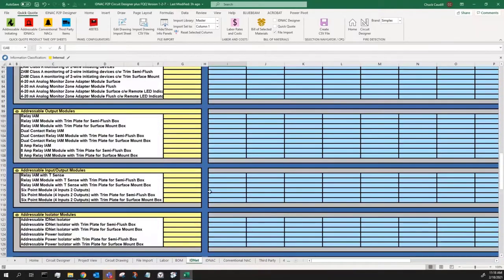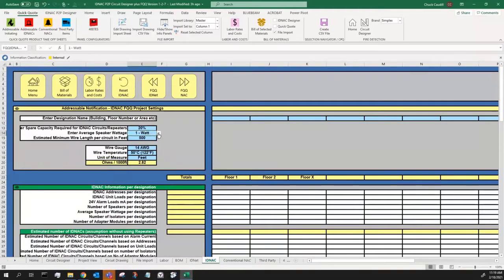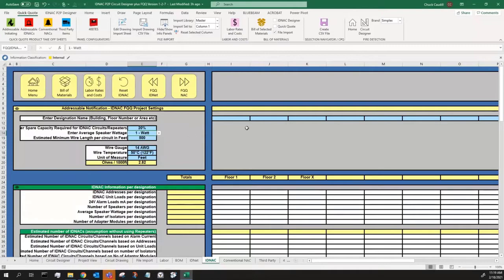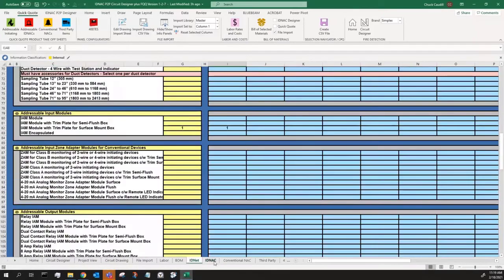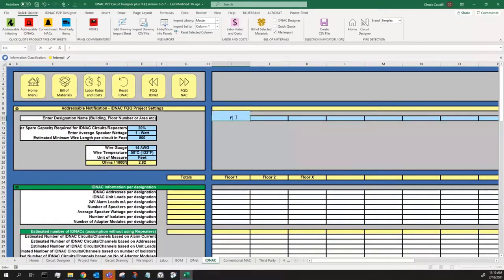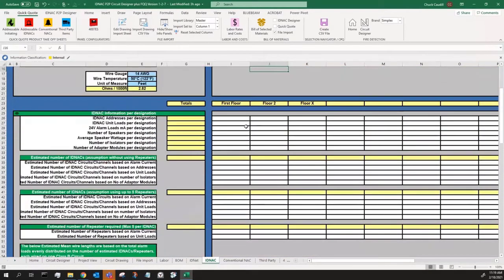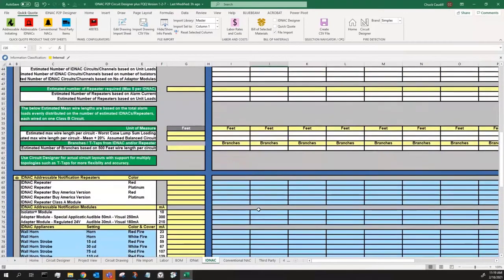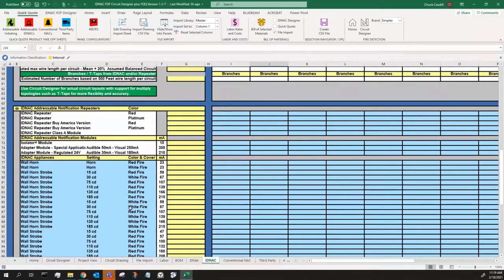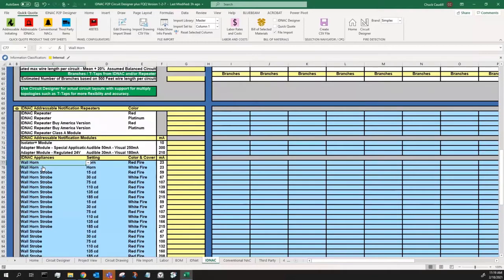Let's move into the addressable IDNAC page. This is set up a little bit differently. You have the 20% spare capacity, but I also have my average speaker wattage. So as I add speakers to it, it will keep a track of how many watts do I need on my amps. This floor one, two, and three that I designated on the first page carries on to the next page as well. If I need something different, a different area, then I can override that by saying this is the first floor. It'll change it on just this page. The center section, again, is our totals. They're all in white. I can't change them. The bottom are all the things that I can modify. Different than the IDNet page is the devices. On IDNet, we listed everything out with all of their different pieces and parts that you use on every single job that has addressable notification.